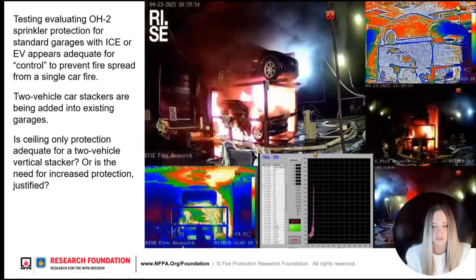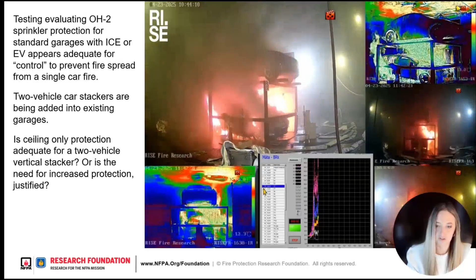We activated all 9 sprinklers within about 10 minutes. A few minutes after that, within 15 minutes, all of the sprinklers beyond the perimeter would have activated as well. We were unable to obtain control, and we ended up losing the underpan of the battery pack on the EV on top, and the battery started falling onto the car below, further intensifying the fire. So a lot of challenges there to address.